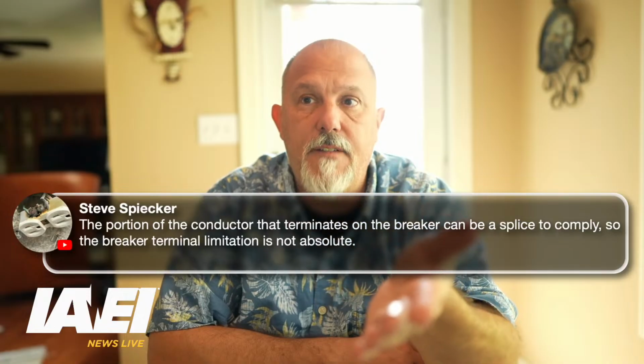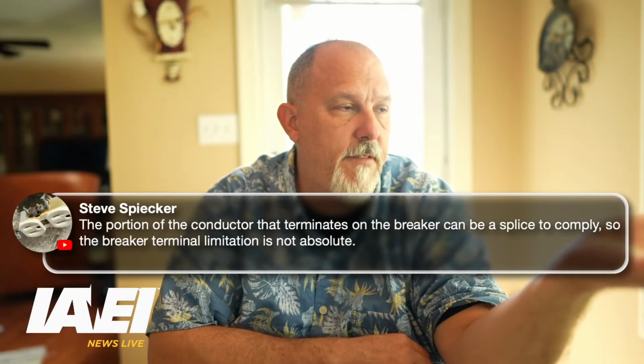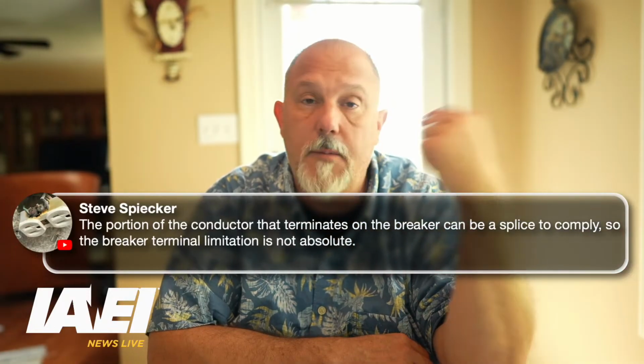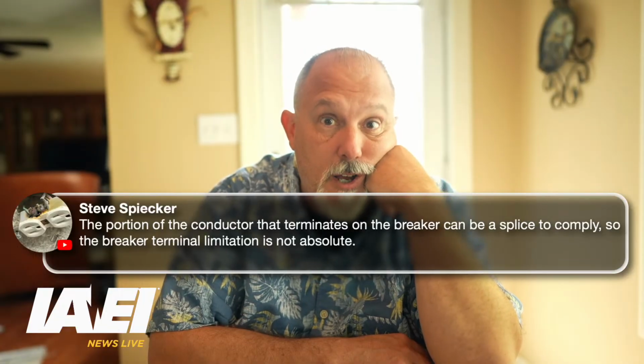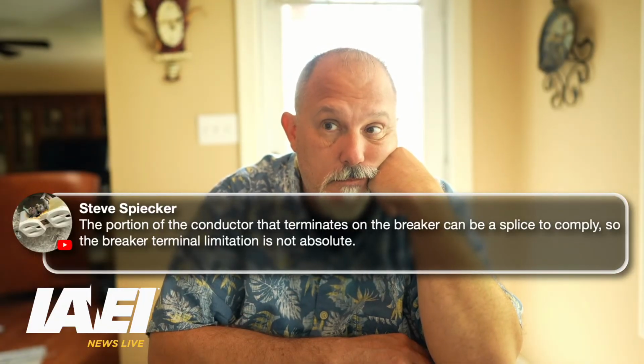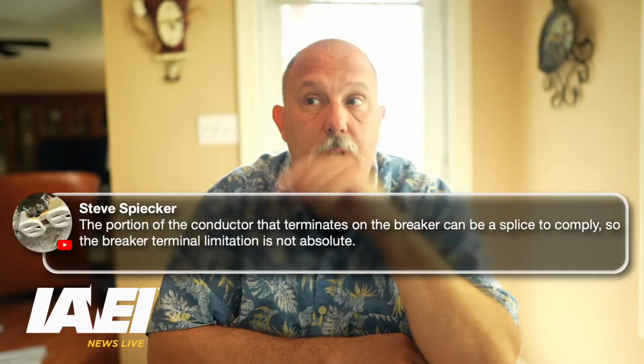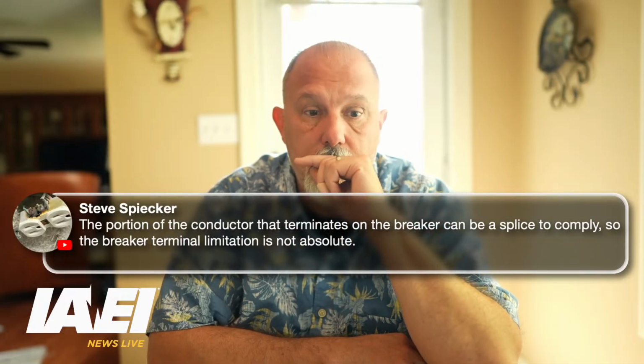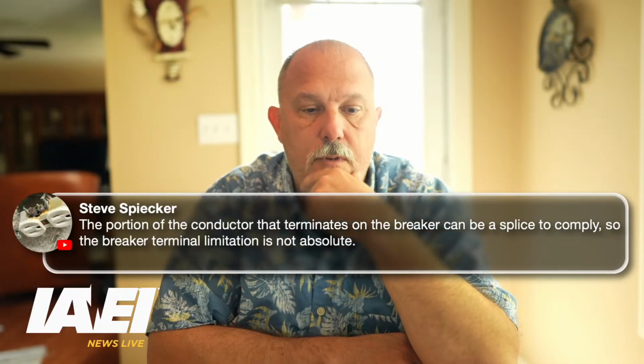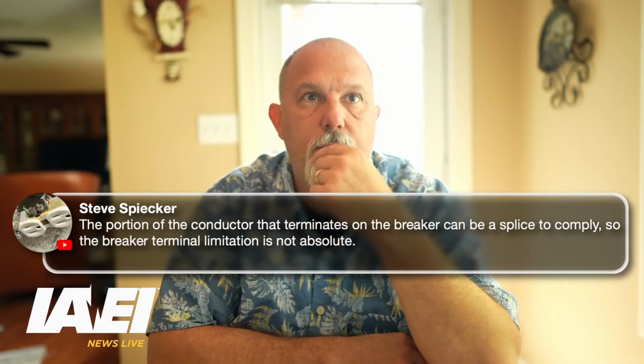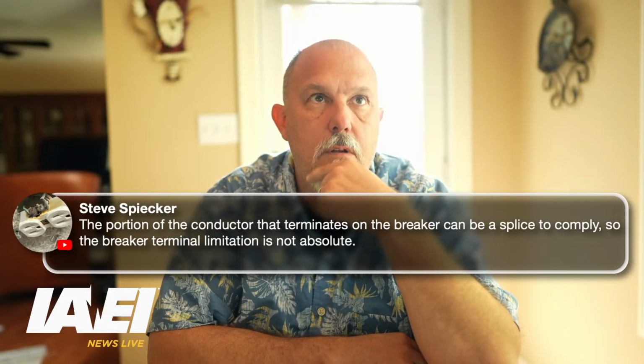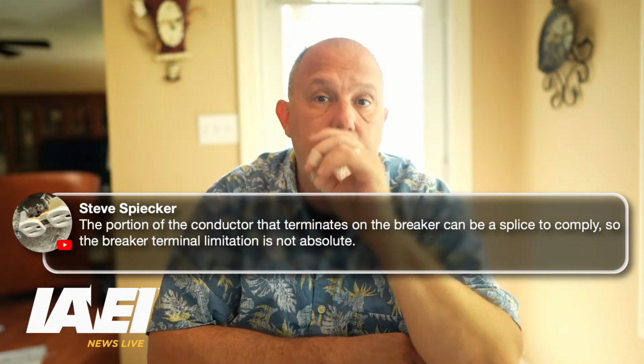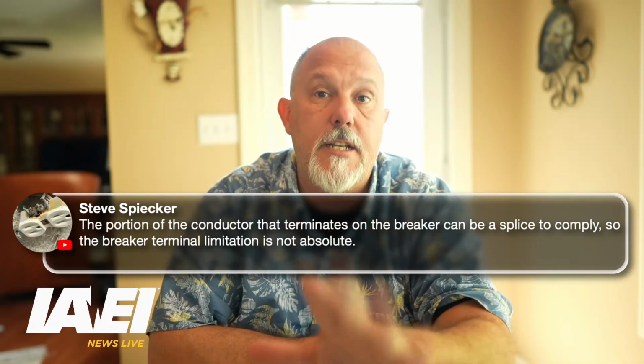The challenge you have, like on a 150 amp breaker, I'm not going to put two different conductors under the same lug. Right? So now if you splice the conductor, a larger or smaller size than the terminals are labeled for. Yeah, as long as you're protecting the conductor at its ampacity.